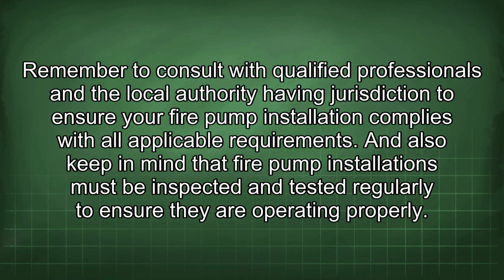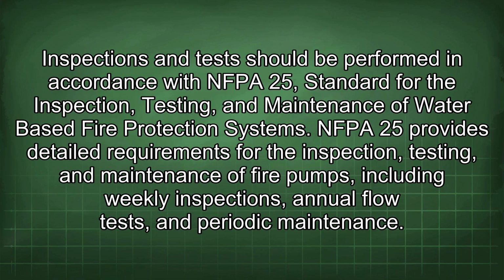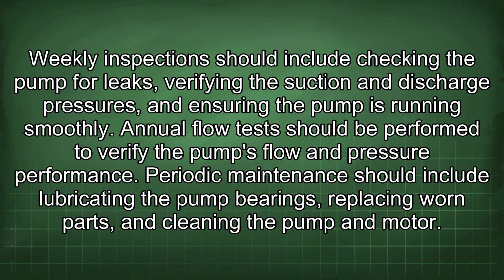they are operating properly. Inspections and tests should be performed in accordance with NFPA 25, the standard for the inspection, testing, and maintenance of water-based fire protection systems. NFPA 25 provides detailed requirements for the inspection, testing, and maintenance of fire pumps, including weekly inspections, annual flow tests, and periodic maintenance. Weekly inspections should include checking the pump for leaks, verifying the suction and discharge pressures, and ensuring the pump is running smoothly.